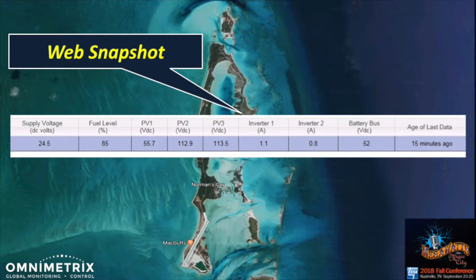This very simple system gives my customer, who has to maintain this far-flung system, the ability to look at the gen battery, gen fuel, the individual values from the photovoltaics, and the current in each of the 2 legs of that single-phase system. It also lets them look at the battery bus in the primary energy storage system. It's a 48 volt design point sitting at 52 volts in this case, so it's right where it should be.